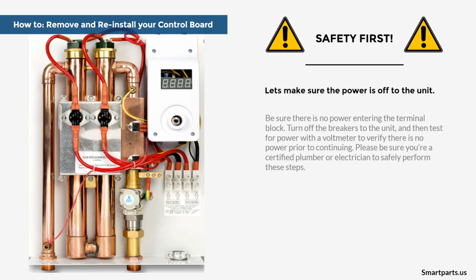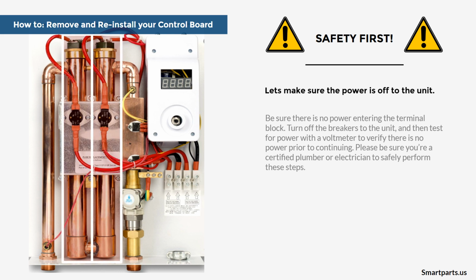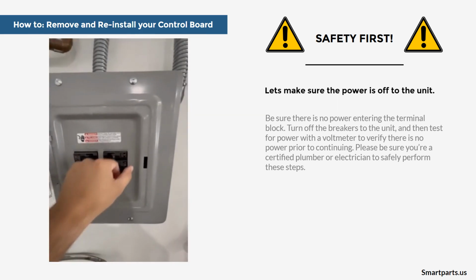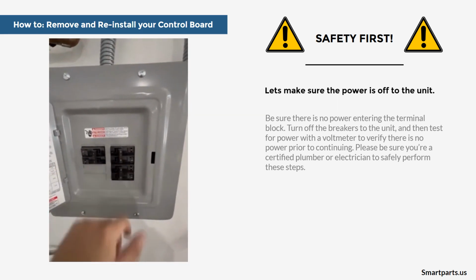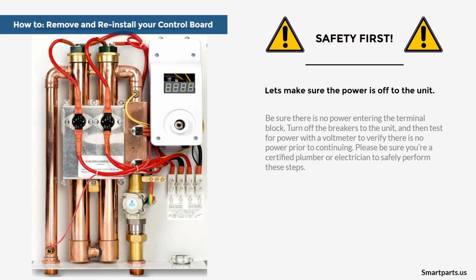So before we begin, first things first is safety. We want to shut off the power to this unit. This unit in front of you here is our demo unit, which is an Ecosmart 18 kilowatt. This has two 9 kilowatt elements, meaning there will be two separate breakers powering this unit. It'll be two double pole breakers, and you want to shut them to the off position. Once we do that, we could go ahead and run back to our unit.